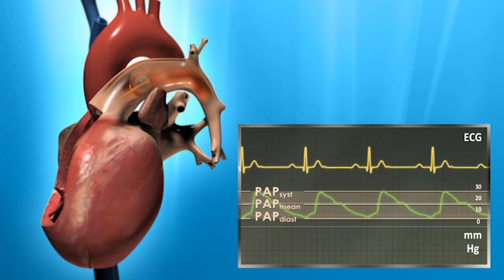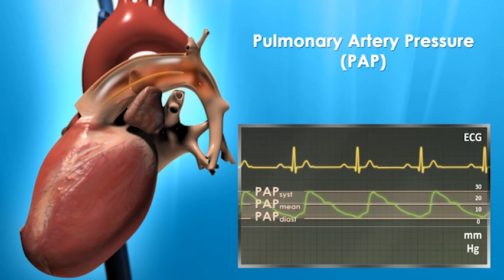After the tip of the catheter has been allowed to float further with the bloodstream through the right heart into the pulmonary artery, the balloon is deflated again and 3 pressure values can be established. As before, the correct position of the catheter is confirmed through monitoring the typical pressure curve for the location. The 3 pressure values measured here at end expiration are the systolic, diastolic, and mean blood pressure in the pulmonary artery. Before the measurements are performed, 0-point calibration is repeated. Values markedly higher than the physiological ones point to pulmonary hypertension.